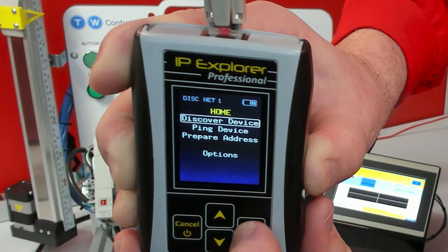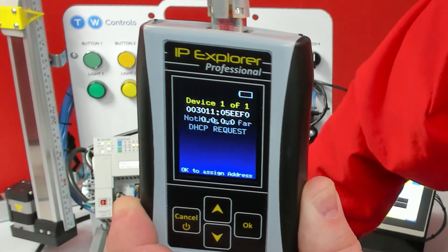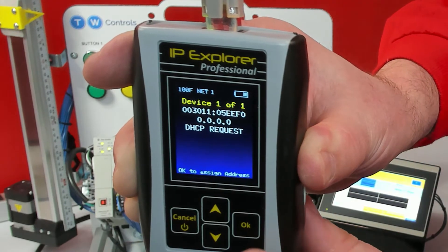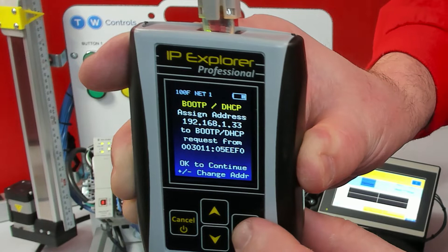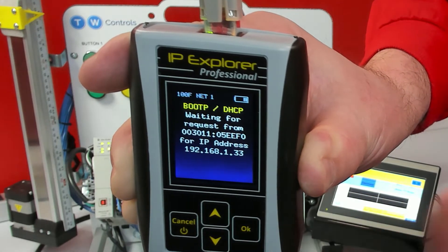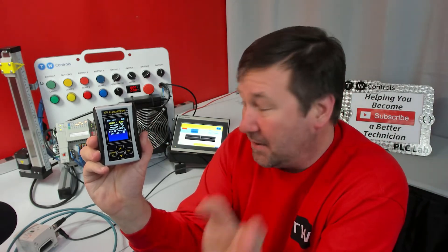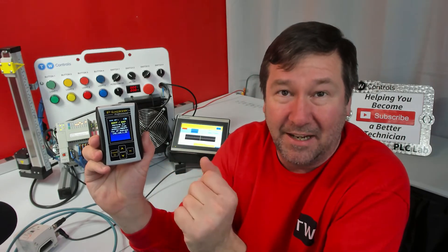Then we're going to go up to Discover Device and power up the SMC. As soon as it comes up with the DHCP request, we'll click OK. We already have the data in there for 192.168.1.33, so we just click OK. If it gets paused on the Waiting for a Request screen, chances are it had to do with the timing of powering up the SMC device and assigning it — just redo those steps and it'll work.